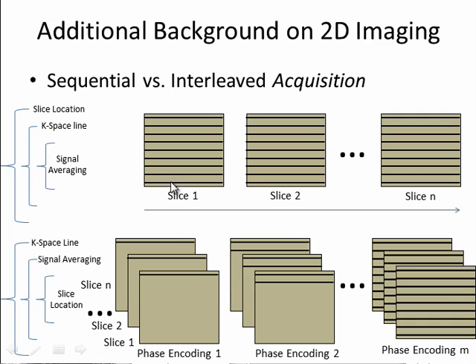Then we would move to the next line, four times, do averaging, and next line, and so on until all the lines for this slice were acquired. Then we move to the outer acquisition loop, which is slice location, so we move to the next slice, acquire the first phase encoding line, average, and so on until we make it to the final slice.